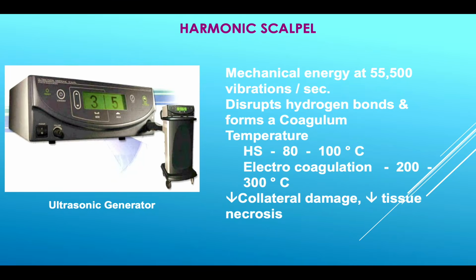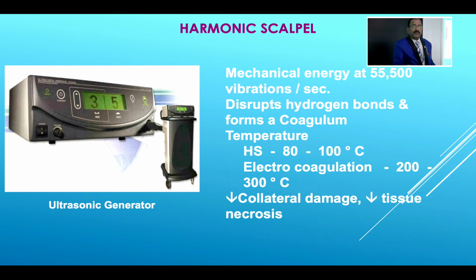Harmonic scalpel is an essential instrument nowadays. It is a must-have instrument. If you want to do the surgery properly, then the harmonic scalpel must be used. It is ultrasonic energy, a mechanical energy which has 55,500 vibrations per second. The harmonic scalpel disrupts hydrogen bonds and then it forms a coagulum. Harmonic scalpel is not a current, it's not monopolar, it's a friction energy.